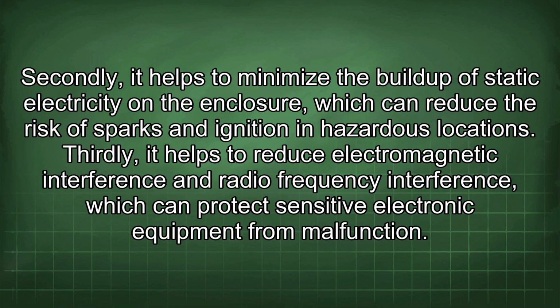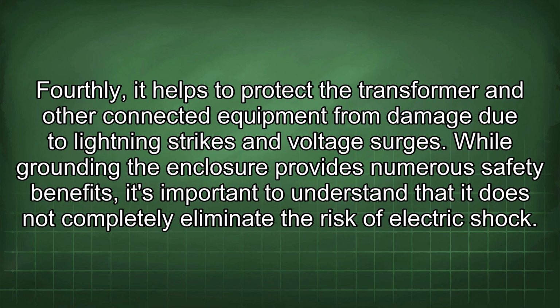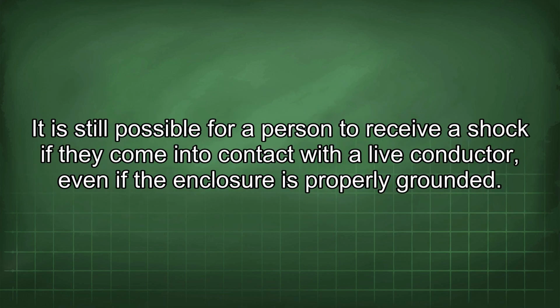Thirdly, it helps to reduce electromagnetic interference and radio frequency interference, which can protect sensitive electronic equipment from malfunction. Fourthly, it helps to protect the transformer and other connected equipment from damage due to lightning strikes and voltage surges. While grounding the enclosure provides numerous safety benefits, it's important to understand that it does not completely eliminate the risk of electric shock. It is still possible for a person to receive a shock if they come into contact with a live conductor, even if the enclosure is properly grounded.